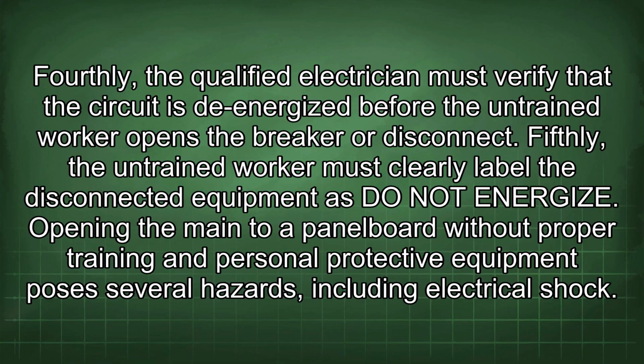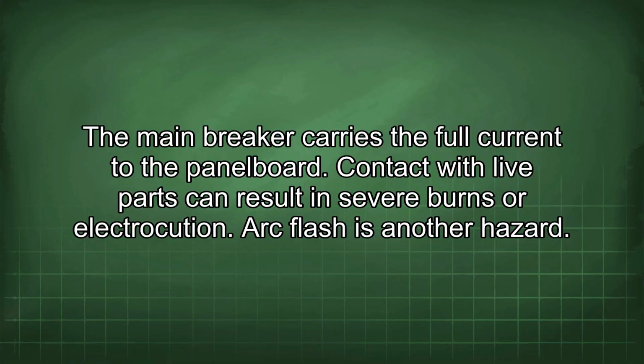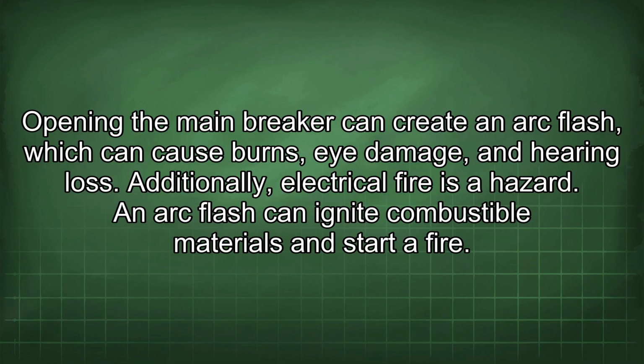Opening the main to a panel board without proper training and personal protective equipment poses several hazards, including electrical shock. The main breaker carries the full current to the panel board. Contact with live parts can result in severe burns or electrocution. Arc flash is another hazard. Opening the main breaker can create an arc flash, which can cause burns, eye damage, and hearing loss. Additionally, electrical fire is a hazard. An arc flash can ignite combustible materials and start a fire.